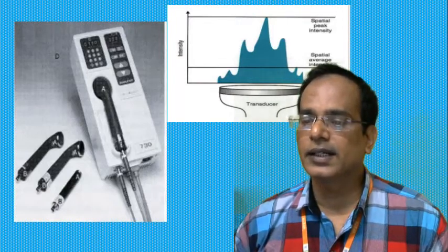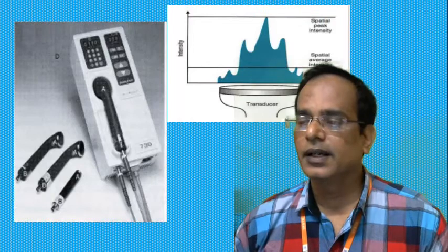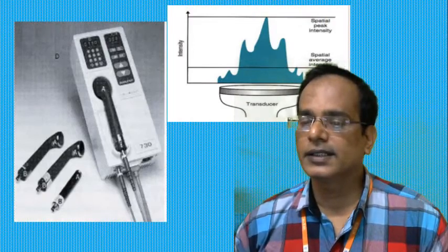A suitable circuit can maintain constantly oscillating electric charges, causing the piezoelectric crystal to change shape at the frequency, and also drive the plate backwards and forwards at the same frequency in any medium with which it is in contact. This amplitude is referred to as intensity, the energy crossing unit area in unit time perpendicular to the sonic beam. It is therefore measured in watts per square centimeter.